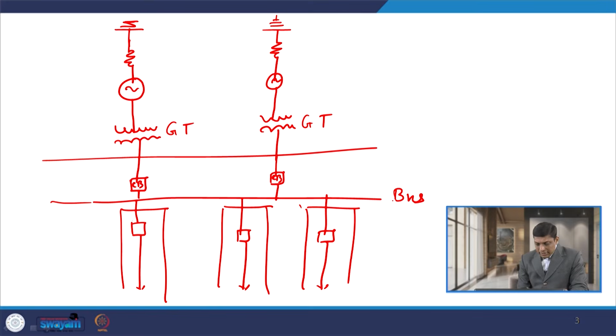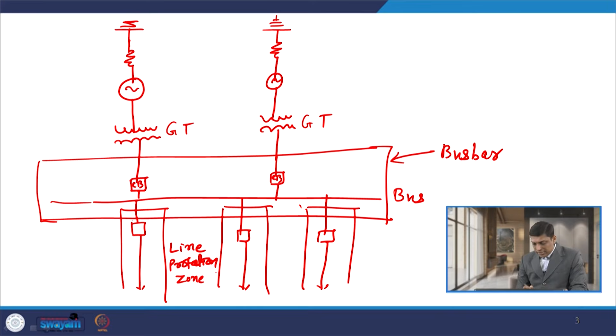Now, if I consider this bus, this bus also has its own zone, and as I told you, all the protective zones are overlapped. So, if I mark the zone for the bus bar, then it has to be overlapped like this. Whenever I say this is the zone for bus bar protection, and this is the line protection zone, you know that both are overlapped. That means if any fault occurs in a particular section, then that section's device has to operate, and if that device fails, then the other zone's device is capable of providing sufficient backup.